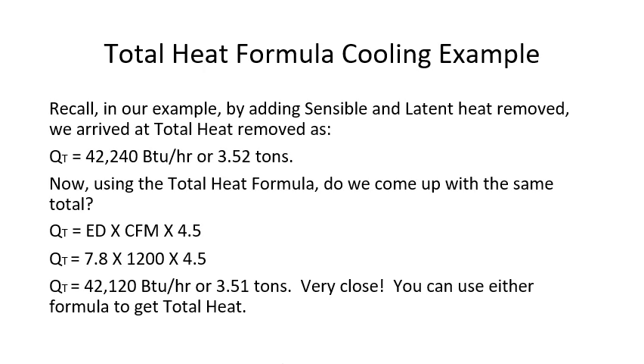Let's use this total heat formula to determine what total cooling was removed from our sample air conditioning problem. In our example, when we added sensible and latent heat, we arrived at 42,240 BTUs per hour of total heat. Let's see if we come close to that same number using the total heat formula. Total heat equals enthalpy difference times CFM times 4.5. Plugging in our values: 7.8 enthalpy difference times 1,200 CFM times 4.5 gives us 42,120 — very close to the previous number. You can use either formula to get total heat, whichever is easiest given the instrumentation and methods you have available.